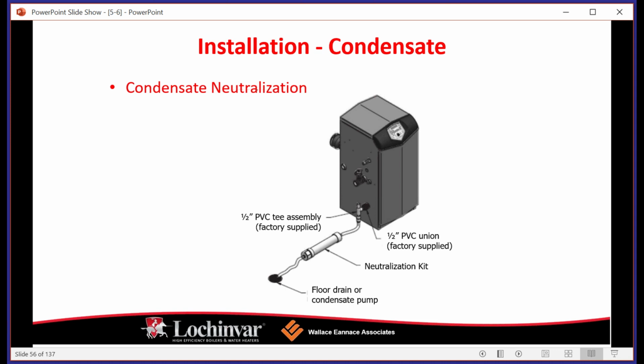So for two reasons, we don't want to dump that acidic condensate into a public drain, a floor drain, or a condensate pump. Bad for the environment, first and foremost. We don't need to be pumping acidic water back into the water table, into our drains, into our sewers, where it's going to run back into the oceans or streams or whatever. Not good. Also very important to remember is that the acidity from an infrastructure standpoint is going to have an issue. So if you have a building where all of your drain pipes, older building maybe, are cast iron, over time the acidity in the water can damage those pipes.